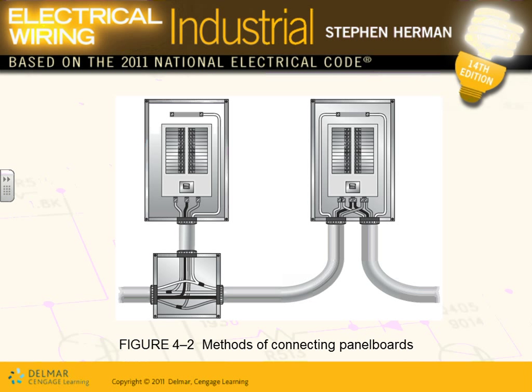For example, when you did your calculation, say your lighting load was 205 amps. You went to a 225 amp panel, cool. But you decided, Darren, your panel, you need only one panel, but you decided to split it into two sections, so you can have one panel on the first floor, one panel on the second floor. Here's one way of doing it.